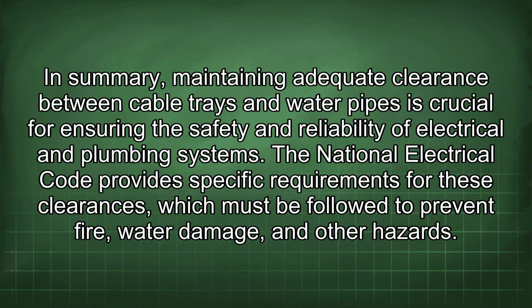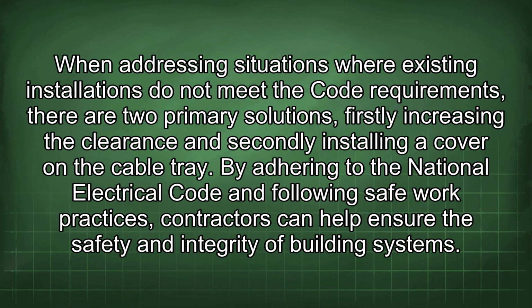In summary, maintaining adequate clearance between cable trays and water pipes is crucial for ensuring the safety and reliability of electrical and plumbing systems. The National Electrical Code provides specific requirements for these clearances, which must be followed to prevent fire, water damage, and other hazards. When addressing situations where existing installations do not meet the code requirements, there are two primary solutions: firstly, increasing the clearance, and secondly, installing a cover on the cable tray.